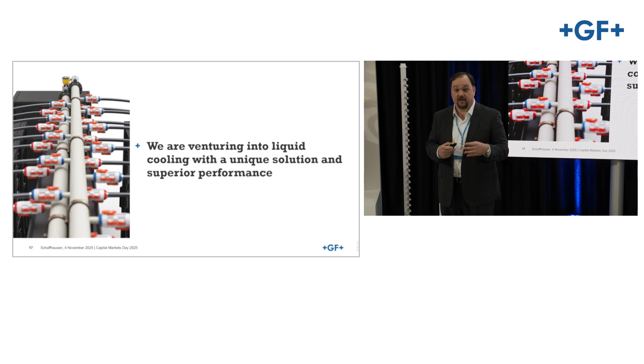When we talk about liquid cooling, fluids are a much better thermal conductor than air. That's why, as we get to about 95 kilowatts per rack, it seems to be the breaking point where the laws of physics start to apply and exert their force. Basically, we can no longer take cold air through the front of the server, exhaust it out the back, and get enough heat rejection to cool these new chips that are super power-hungry and super powerful, whether GPUs, TPUs, or in some cases CPUs.